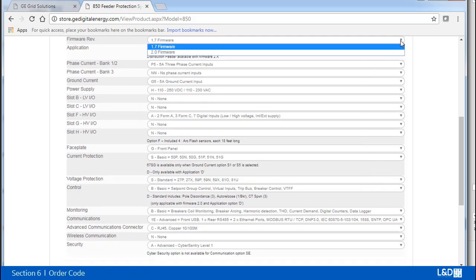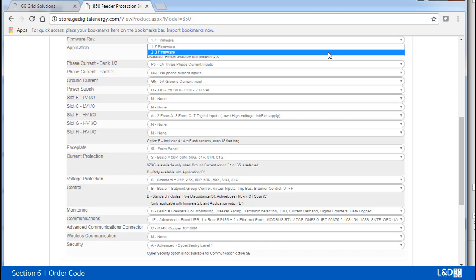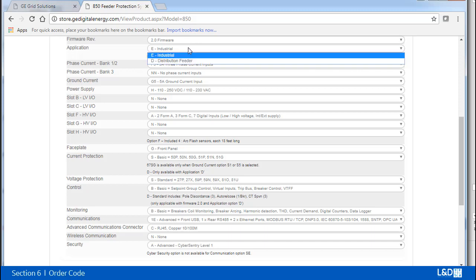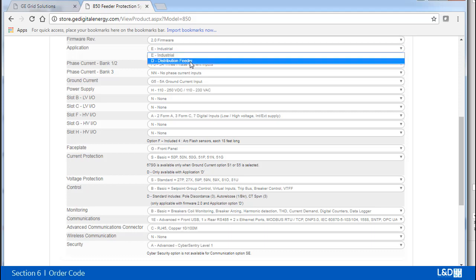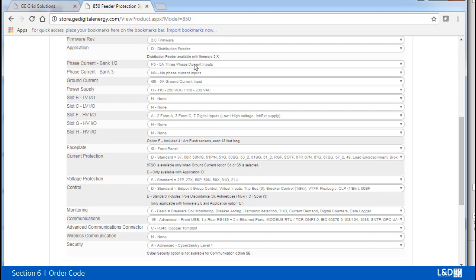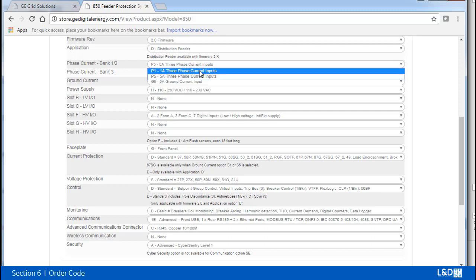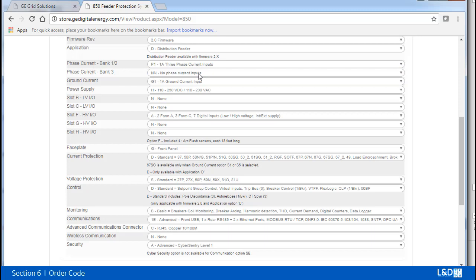The first is the firmware. So far the latest release is 2.0, so I can choose the latest version. Then I get application options: E for industrial, D for distribution. For example, I can choose distribution. Then I can choose the CT secondary and the second bank of current. Ground can automatically populate into 1 amp to match the phase CT. The power supply, high and low.